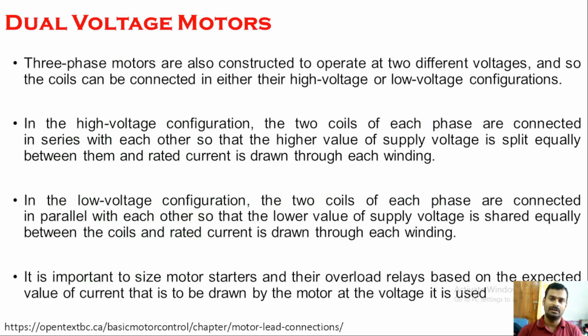These are like other three-phase induction motors, but these motors can operate with two different voltages without changing their performance. Most of the performance parameters like torque, speed, power, power factor will be kept constant with respect to either high voltage configuration or low voltage configuration. So in either configuration you will achieve the same power factor and same torque, but the voltage and current differences will be maintained.